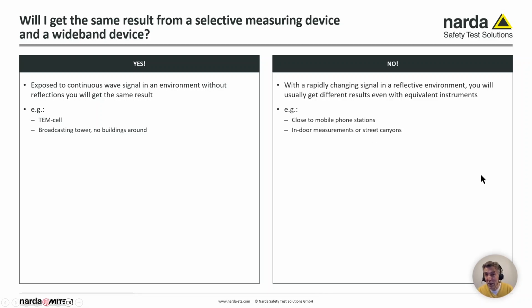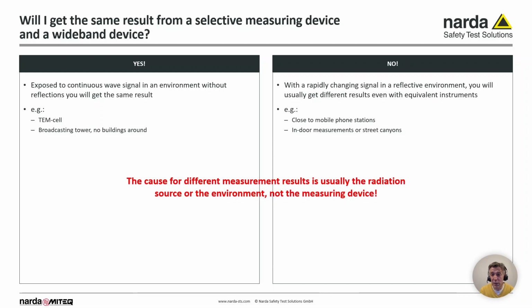You will not get the same measurement result if you are in an environment where the signal is changing rapidly. And remember, your mobile phone is changing its output power every millisecond. So this is the worst source you can have for comparing instruments. And reflections are also the death of any comparison of test equipment. So even equivalent meters will not give you the same readings because they are in different positions at different times and so on. It's a little nightmare. Therefore, we have special measurement procedures where you have to do an averaging or a max hold over a certain area so that you get comparable measurement results. The cause for different measurement results is usually the radiation sources or the environment and not the measurement device. Okay, so always think about what you are doing. The measurement device can only show you the result at the following point at the following time. Everything else you have to think about.